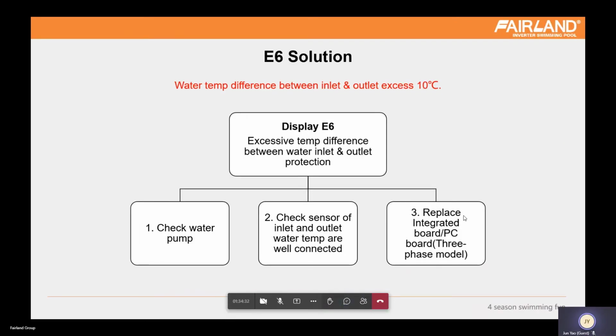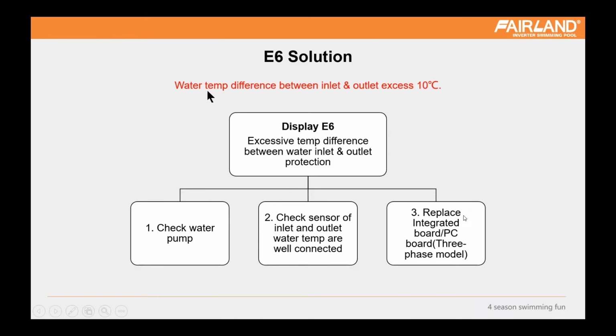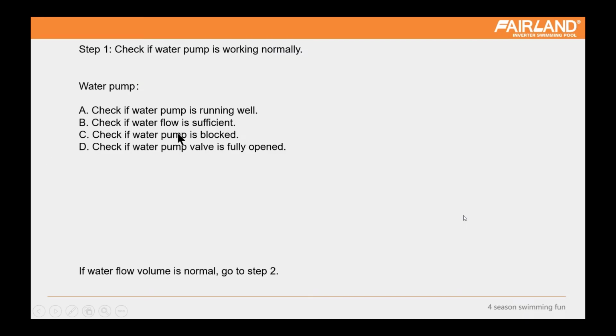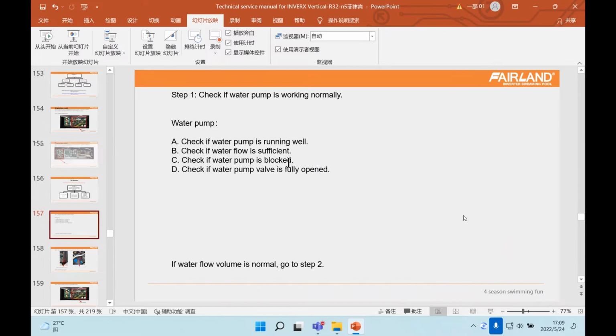This is what we call the water protection, because it will make the water temperature difference between inlet and outlet exceed 10 degrees. So normally when E6 happens, we will check if the water volume is normal or not. And of course, you need to check the display, to see if it is really a 10-degree difference, because sometimes maybe it's a program issue.